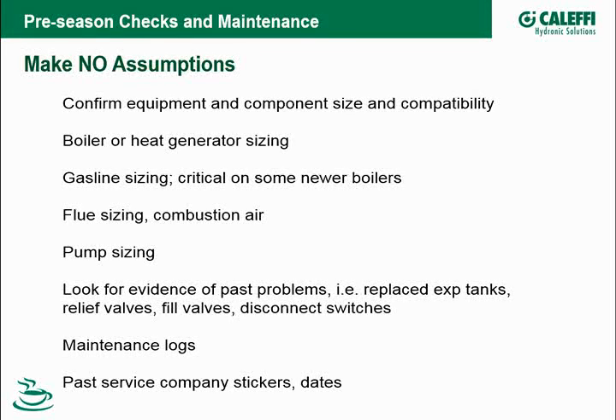Either the boiler's been oversized and the pumps. You know, people have changed brands or changed pumps over the years and just probably put in whatever they had with them that day or was on the truck. So they could be running way off or way to the top, to the bottom of their curve, who knows. But we'll show you a little bit about how to use sizing information from the manufacturers and put a system curve over a pump curve and determining the operating point on that curve. So stay tuned for that towards the end of the year.